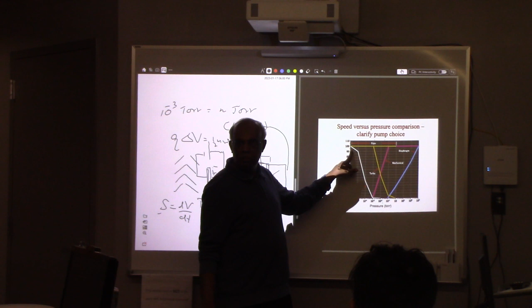So then you'll see the pumping speed increases at very low pressures - they work very well at very low pressure. You can see the ion pump's pumping speed is really high at the lowest pressure, because that's true, right? Lowest pressure means there are no air molecules, so the pump can easily work at much higher speeds. But if you go to high pressure, that means you have a lot of molecules, so your pumping speed is slower.